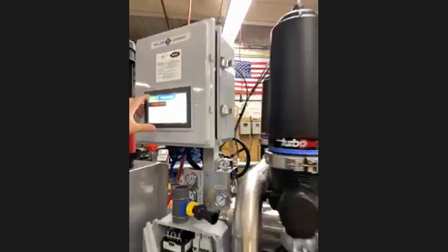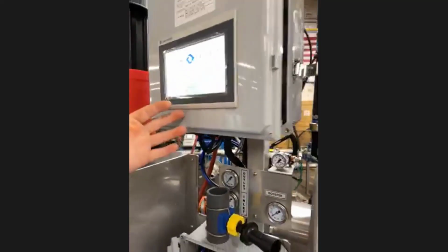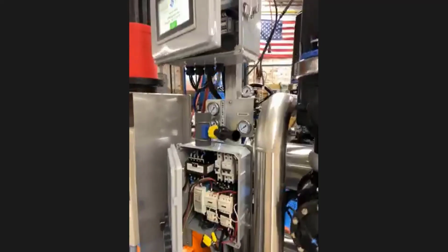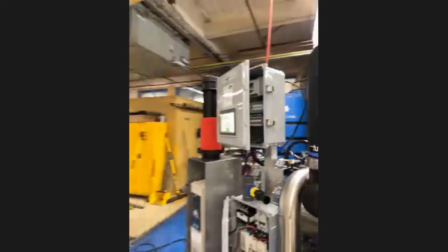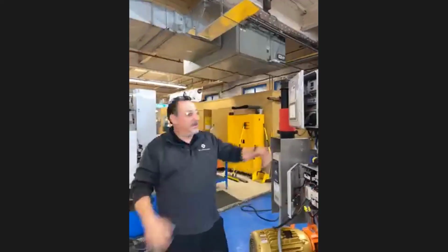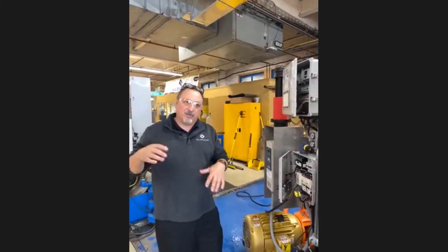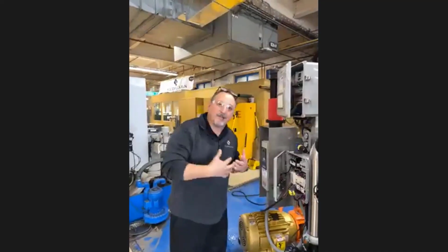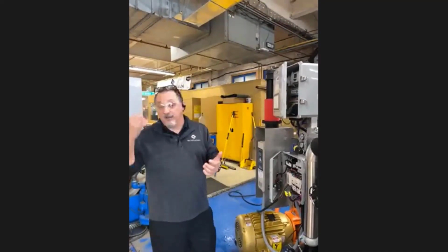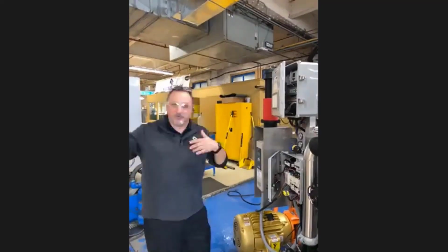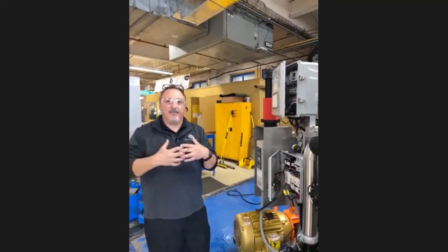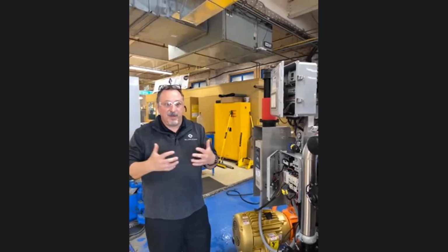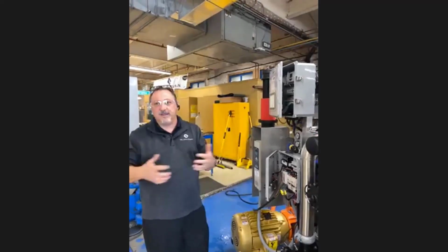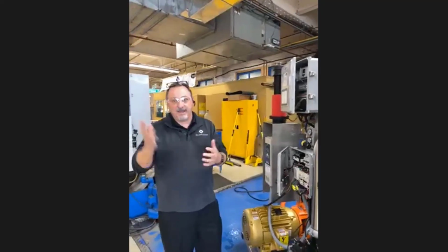So anything like that can be done with these screens. They're all touch screens. So you can take this screen, send the Ethernet out, put it in the control room, plug in the Ethernet. This is the screen you're going to see. You can make all those changes. Now, granted, it's not like a chiller or maybe a cooling tower. It really should be locked down. The issues that we get calls on is when somebody's touching them and changing durations or changing this or changing that, then you have some issues. But if you want that information, such as pressures or anything like that, that can all be sent out through the BACnet or through the Ethernet, whatever you'd like.